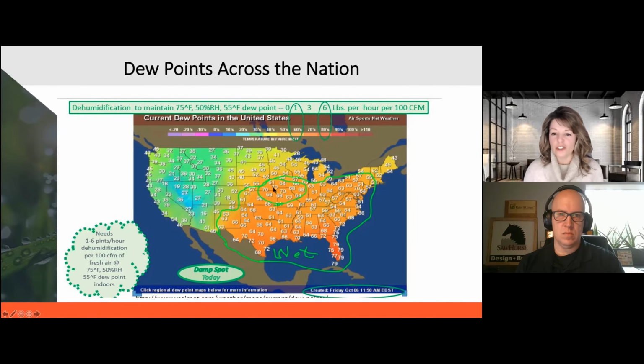And I've got another dew point map that shows where we would consider green grass climates. This is where we need to be thinking about some form of dedicated dehumidification, whether it's the whole house or a basement and crawl space during certain times of the year. I've got a dew point map from September that shows 74-degree dew points up here in Maine. We're seeing more and more of these dew points that we typically only saw in the South making their way farther north and lasting for longer periods of time.